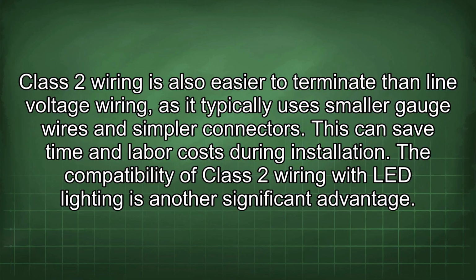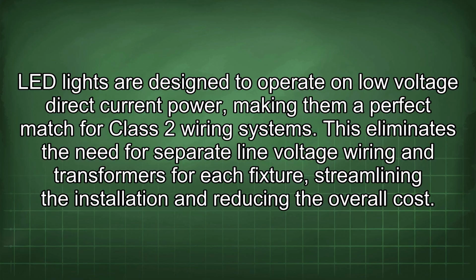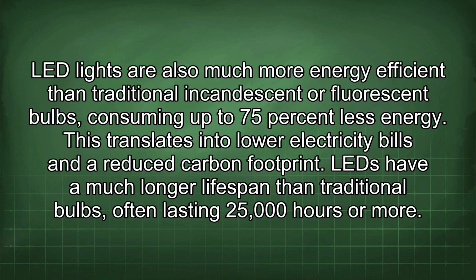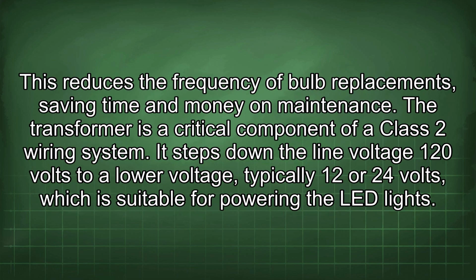The compatibility of Class 2 wiring with LED lighting is another significant advantage. LED lights are designed to operate on low voltage direct current power, making them a perfect match for Class 2 wiring systems. This eliminates the need for separate line voltage wiring and transformers for each fixture, streamlining the installation and reducing the overall cost. LED lights are also much more energy efficient than traditional incandescent or fluorescent bulbs, consuming up to 75% less energy. This translates into lower electricity bills and a reduced carbon footprint. LEDs have a much longer lifespan than traditional bulbs, often lasting 25,000 hours or more. This reduces the frequency of bulb replacements, saving time and money on maintenance.